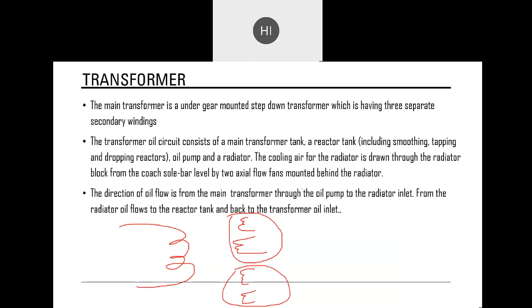This is an oil cooled transformer, with a rating of 1000 kVA. In the primary winding, ideally we have 25 kV at 40 amperes. In the secondary winding for traction, we should ideally have 782 volts at 1280 amperes.